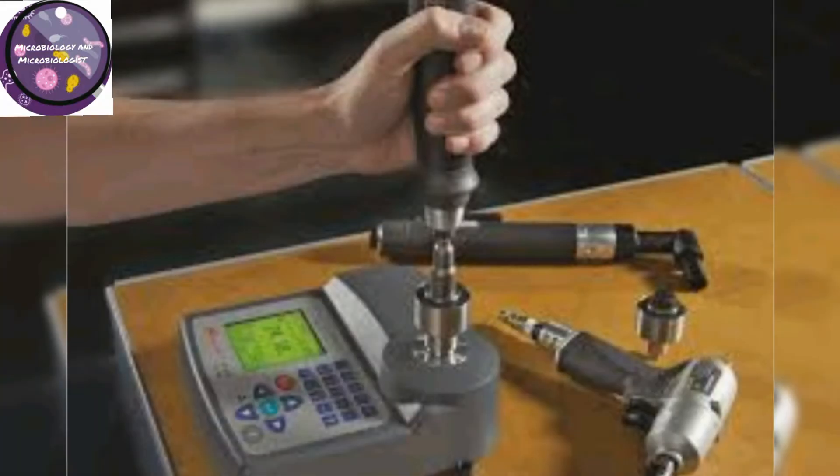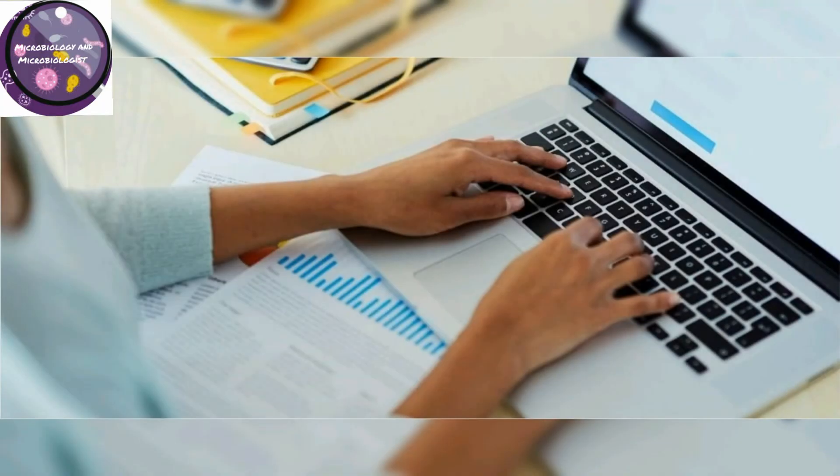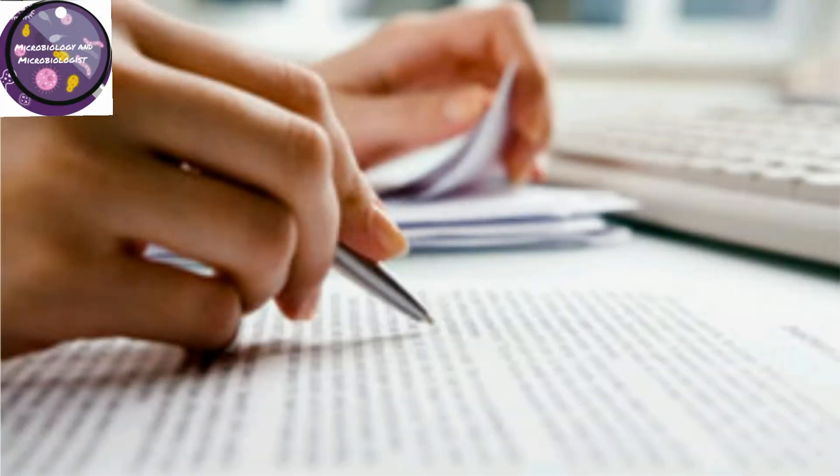Verification is something more that we do on daily basis or as per frequency to check our instruments. Validation is a documented process and it's not only related to instruments. It is also a concern of process and product.